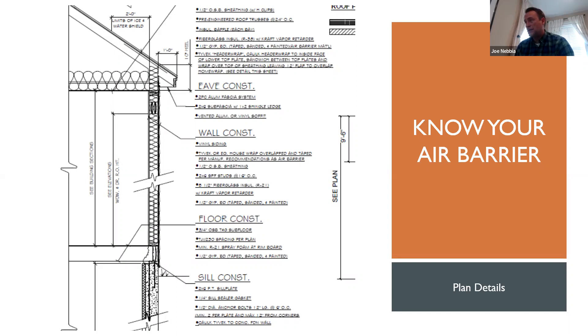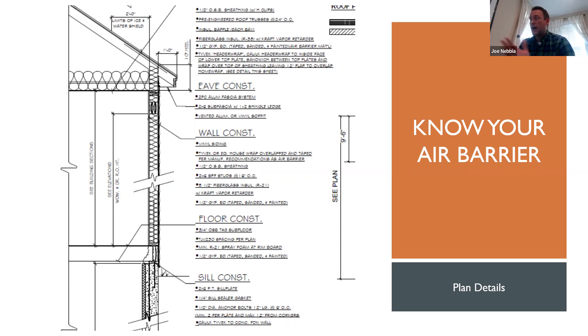You need to know where your air barrier is in order to effectively implement it in the field. It's important that the details are on the plans. If your air barrier is building paper on the exterior, that needs to be detailed and there are certain details that have to happen. If your air barrier is using the drywall on the interior, your air sealing details are going to look a little bit different. If you can't track where that air barrier goes, you're going to miss something. That's an important part of planning a house that has to comply with the IECC.